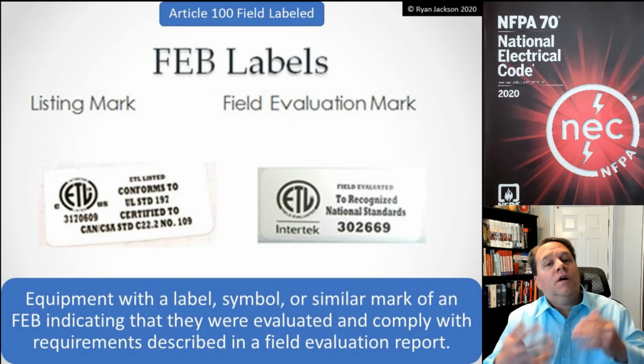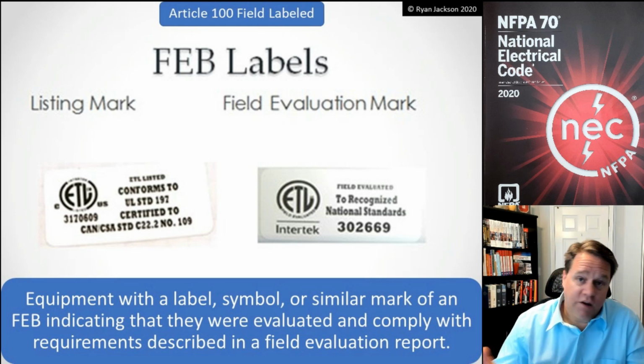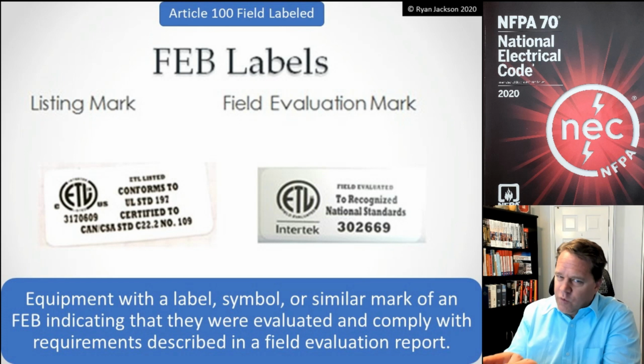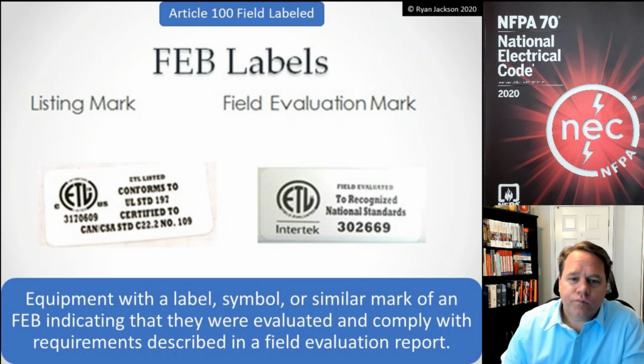All right, so there you go. That would be a field labeled piece of equipment. It's not listed, it's not equivalent to listed, but most inspectors would agree that field labeled equipment is good enough if the code requires listed.